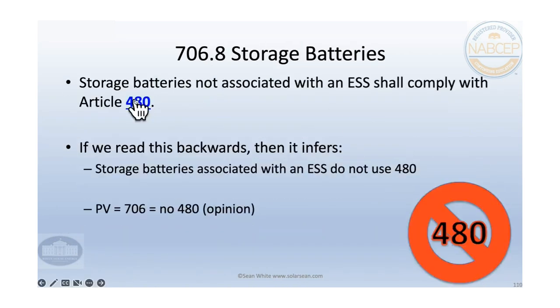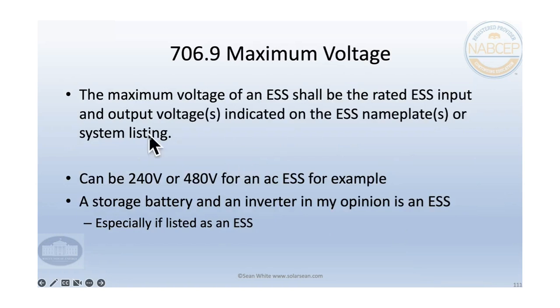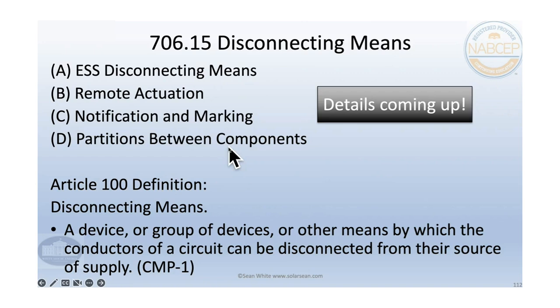So storage batteries, like I said before, we're not doing 480 here. And the maximum voltage shall be the rated input and output voltages. So pretty much it's just kind of obvious. Maximum voltage is going to be what it says. And typically the maximum voltage of an energy storage system is going to be AC. So we're looking at 240 or 480 volts, or of course 208, something like that.